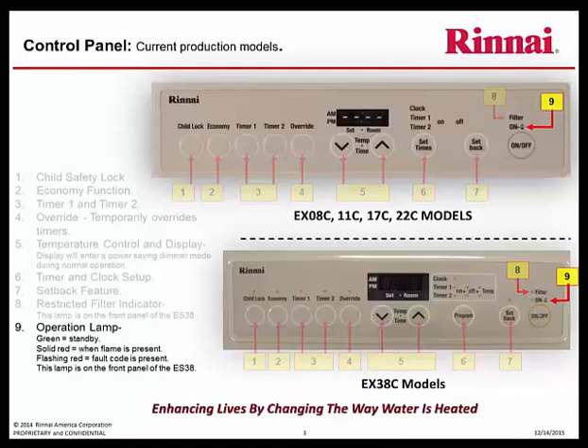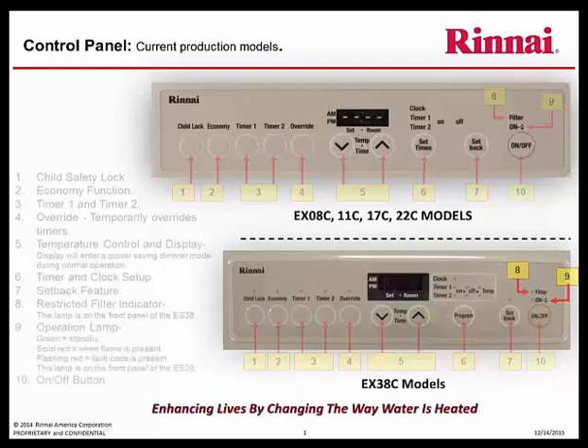Operation lamp. The functioning of this lamp is important as it gives you the current status of the heater. Green is standby, meaning the unit is powered on but not operating. Solid red means flame is present and the furnace is producing warm air. Flashing red indicates a fault code is present. And finally, the on-off button.